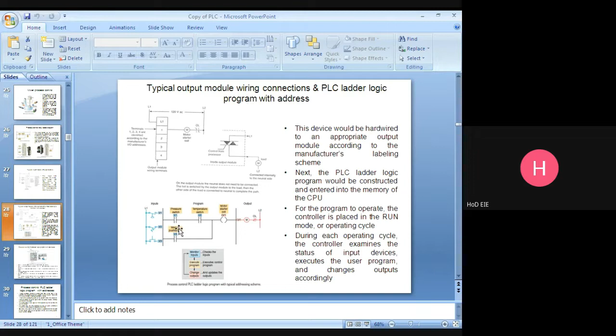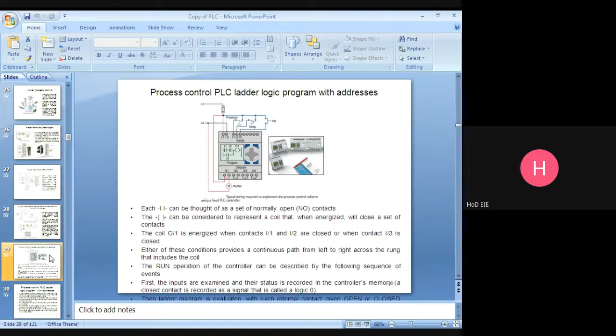The pressure switch, temperature switch, manual push button and motor starter coil each are given an address. Here you are using only the contact and coil. In PLC, what are we using? Contact and coil. The output is a coil. This one is the motor starter coil, and this one is for overload protection. Are you able to understand this? This is the PLC diagram of the process. Here we are using contact and coil only. Got it?